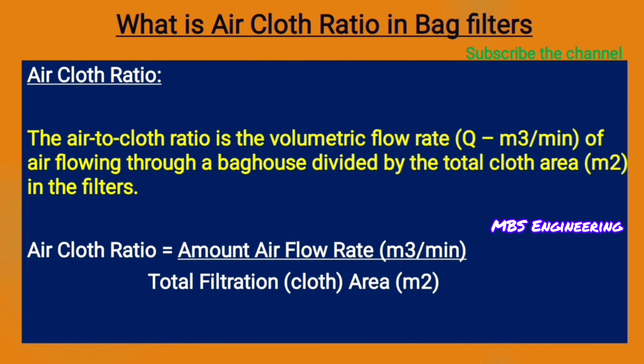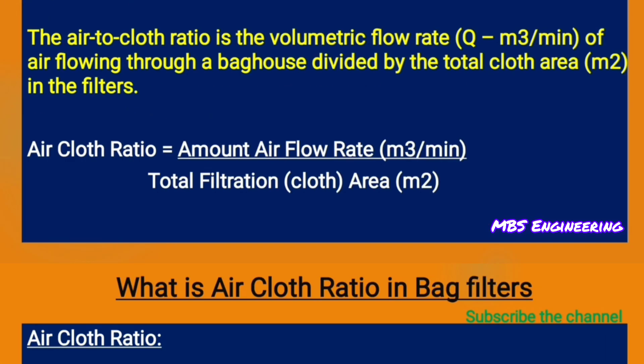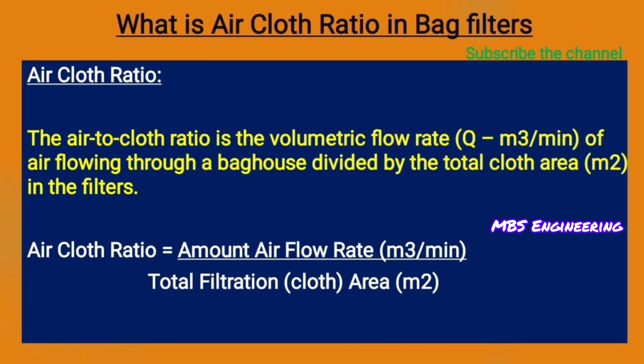Now we are going to understand the air-to-cloth ratio in bag filters. The air-to-cloth ratio is the volumetric flow rate of air flowing through a bag house divided by the total cloth area in the filters. The formula is: air-to-cloth ratio equals the airflow rate in cubic meters per minute divided by the total filtration or cloth area in square meters.